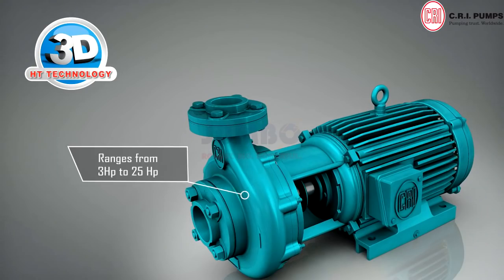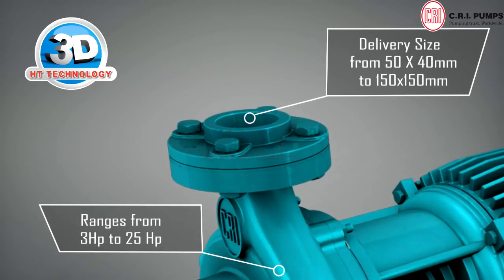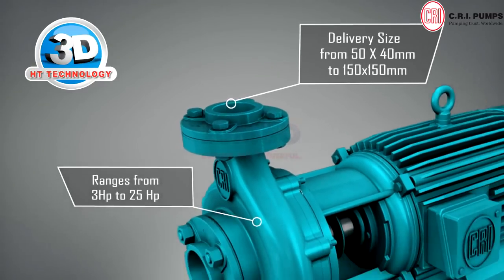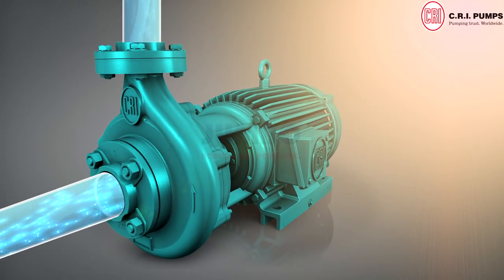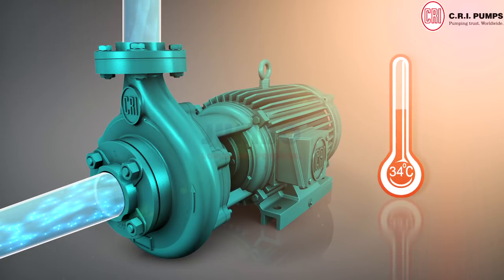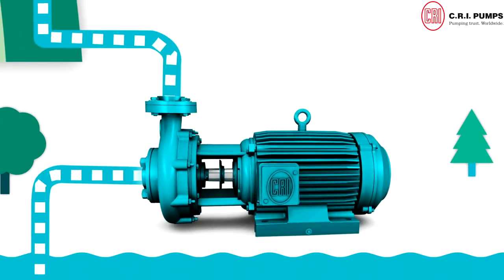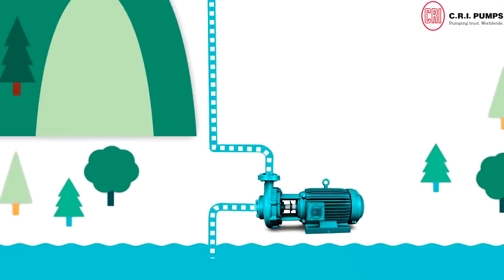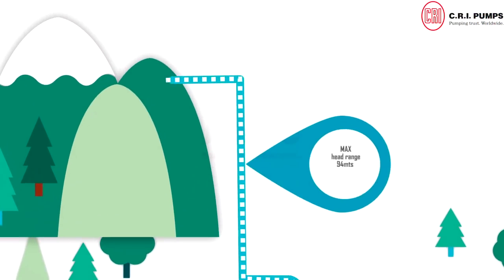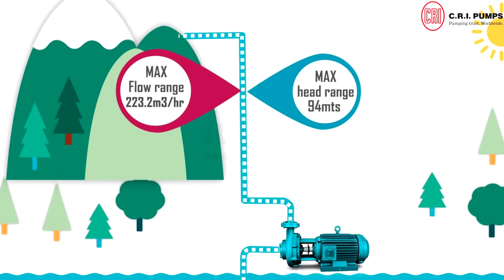Star-rated CRI 3D HT Jumbo Monoblock Pumps range from 3 horsepower to 25 horsepower, with delivery size from 50x40 mm to 150x150 mm. Jumbo can handle a maximum ambient temperature up to 104 degrees Fahrenheit, 40 degrees Celsius, with a normal flow rate of 23 LPS, 82 cubic meters per hour, maximum head range up to 94 meters, and maximum flow range up to 223.2 cubic meters per hour.